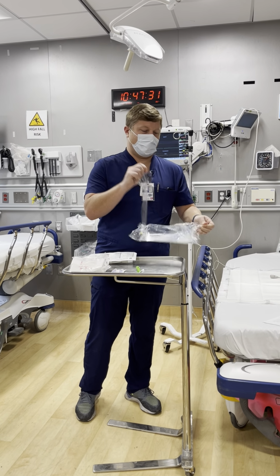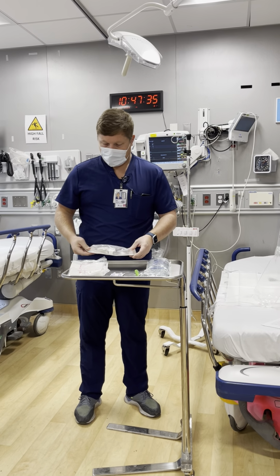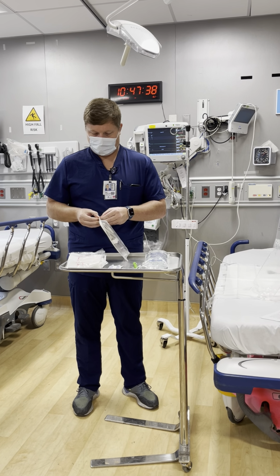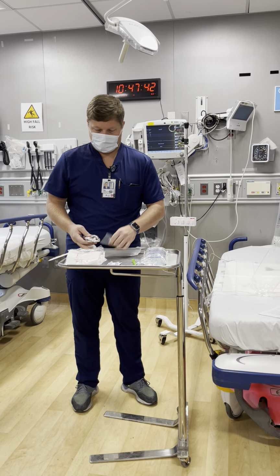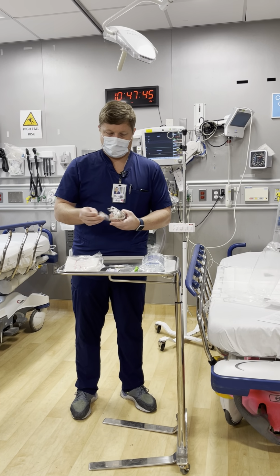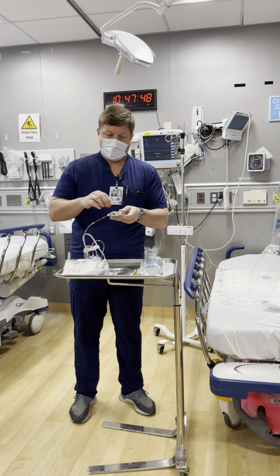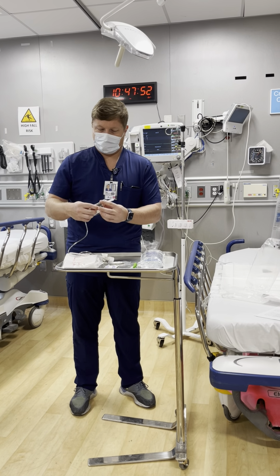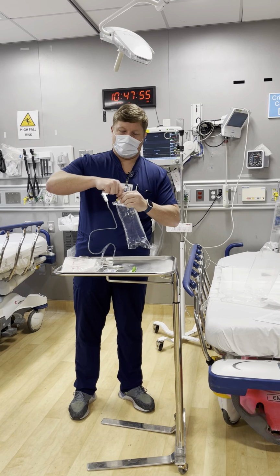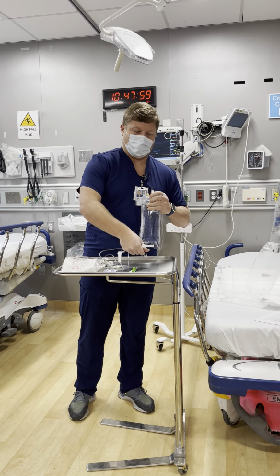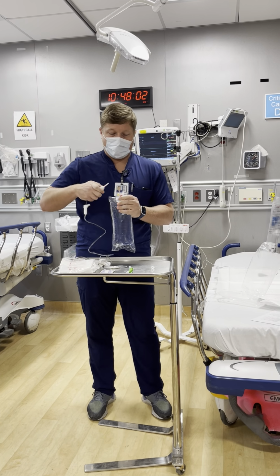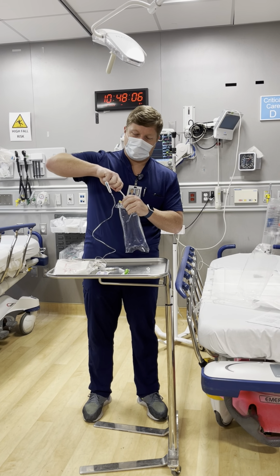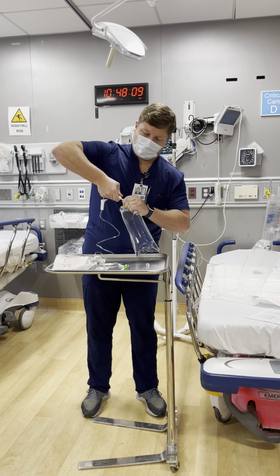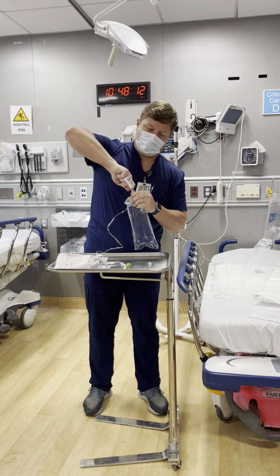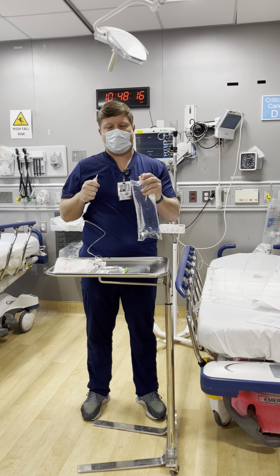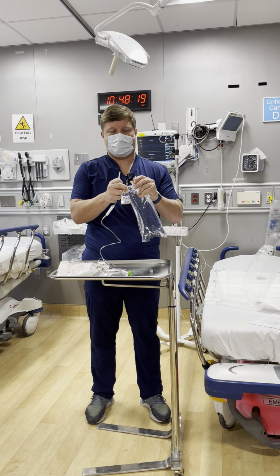So the first thing we're going to do is open up your saline, and then your transducer setup. And then we're going to open everything up. Okay, you're gonna get to the spike, and the first thing you're going to do is open up your saline. We're gonna do a procedure called burping the bag, because you don't want to have any air in your line, because whenever you end up priming your A-line tubing, you can end up with air bubbles, which will end up giving you a dampened result. All right, so once you spike it, you can unspike and express all the air, where there's nothing but fluid left in the bag.